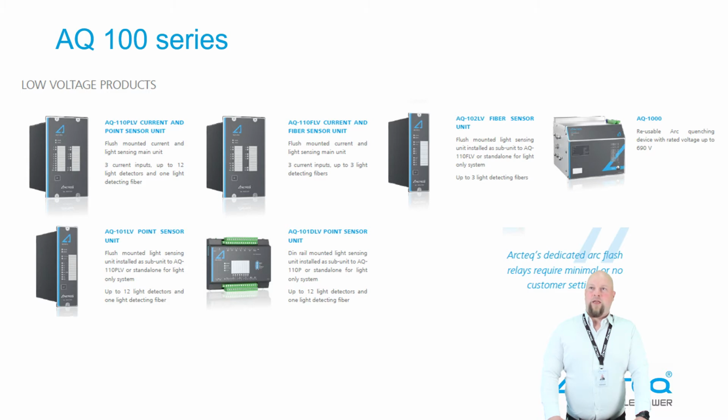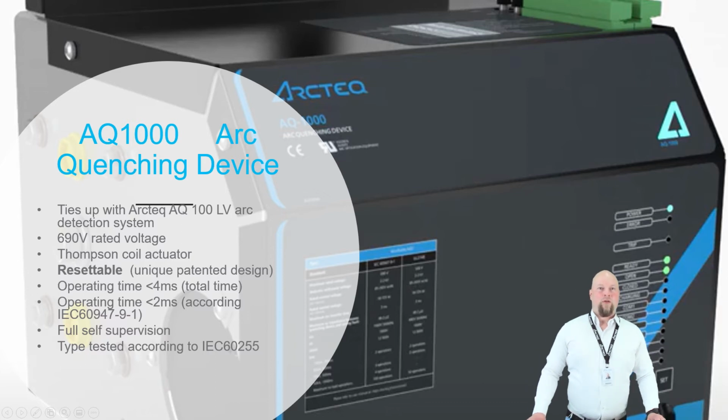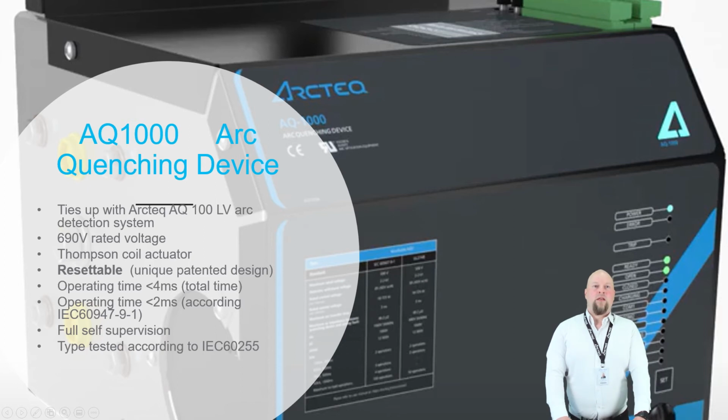All these units can be equipped together with a reusable arc quenching device called AQ1000. That is the only reusable, resettable equipment of its kind in the world. It has a 690 volt rating. It is a unique patented design, and the total operation time is less than 4 milliseconds, from the actual fault to total zero voltage. Operating time according to standards is less than 2 milliseconds, and this is the mechanical closing time. This unit has full self-supervision and is type tested.